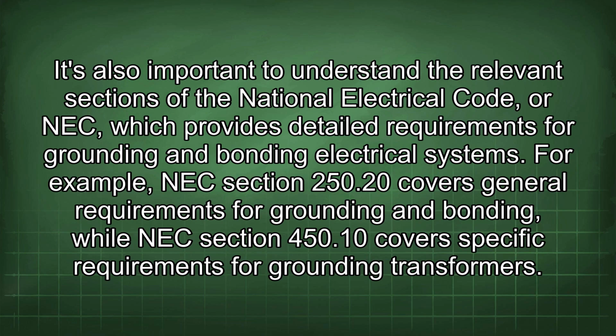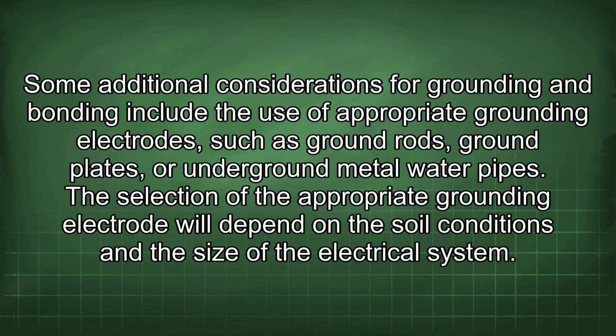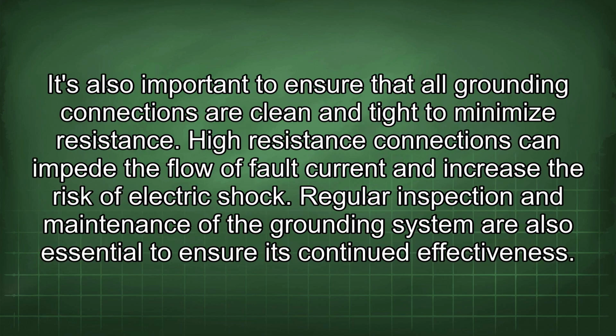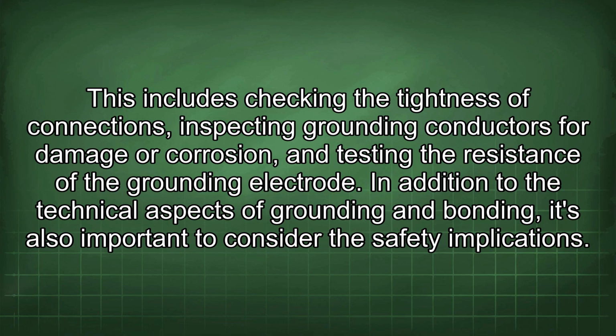grounding transformers. Some additional considerations for grounding and bonding include the use of appropriate grounding electrodes, such as ground rods, ground plates, or underground metal water pipes. Selection of the appropriate grounding electrode will depend on the soil conditions and the size of the electrical system. It's also important to ensure that all grounding connections are clean and tight to minimize resistance. Higher resistance connections can impede the flow of fault current and increase the risk of electric shock. Regular inspection and maintenance of the grounding system are also essential to ensure its continued effectiveness.